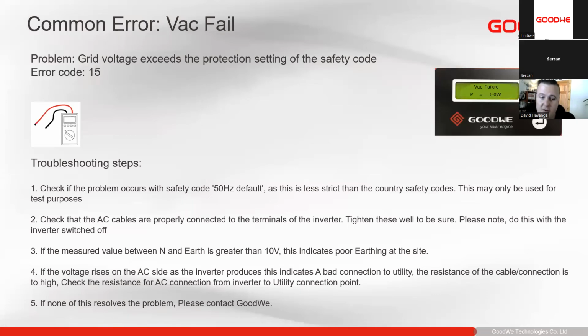Just another thing to add, if you're having the rising voltage, you can always take a multimeter and measure the voltage by the breaker of the inverter. If you see the same voltage there as what's on the inverter, then we can start to measure further down the line. Some countries might have a very small supply from the utility, and it could be a utility supply issue as well, that it will be out of the grid voltage range. If it is out of the grid voltage range, then the utility company needs to be contacted to rectify that. It's not something on site that one can rectify from the inverter side.